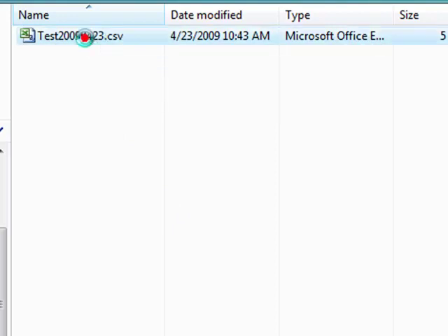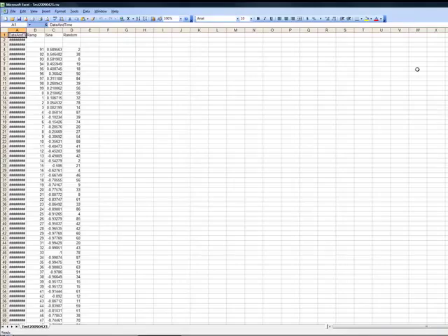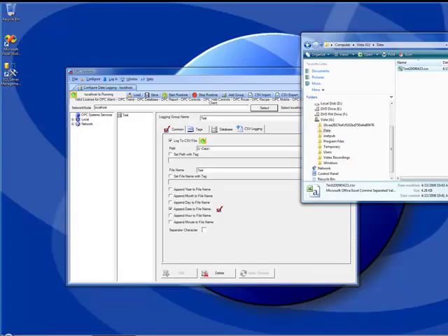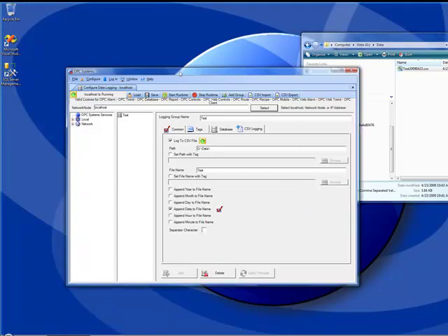So now when we double-click on the file again, we see that we have lost no data. That is the buffering feature of opcsystems.net, that if a database engine, or a CSV file, or even on the data source, if it's temporarily lost, that all data will be provided when the connection is re-established. By default, the data buffering feature is using RAM.